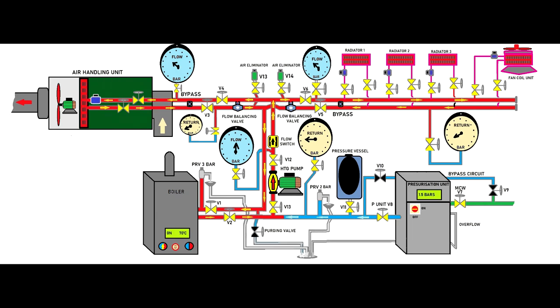So you start the boiler and the system starts to heat up. As you will see, the actuator starts working and it controls the flow through the radiators. I would set this actuator to maximum to make sure that the flow is going freely through the radiators and through the actuator, to make sure that all the pockets will be circulated through the system to be eliminated by the air eliminators. Meantime, the pressurization unit will compensate all the losses governed by the air elimination.